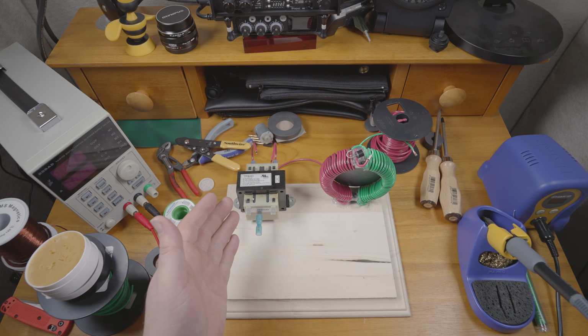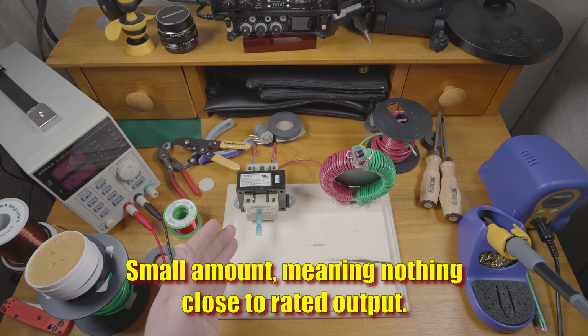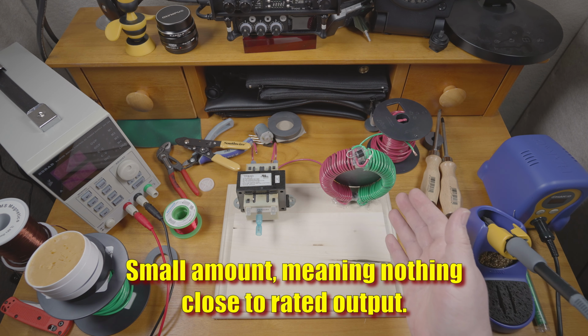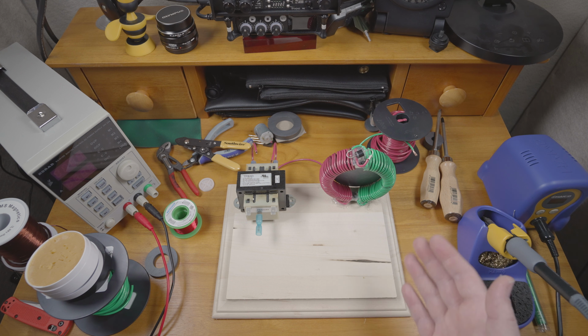Basically, this transformer might be able to produce a small amount of output with a pulsed DC input, but if these coils actually manage to create any meaningful power, it would likely just burn up the transformer. Pulsed DC can be used in specific transformers, or if specific steps are taken to prevent the transformer from reaching saturation. But with this type of transformer and this application in general, it probably won't work at all, and it's definitely a ridiculously inefficient and ineffective way to do it.